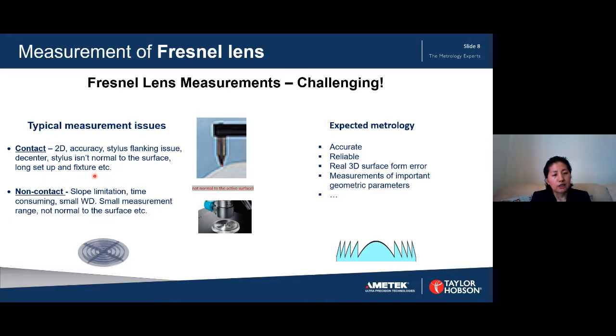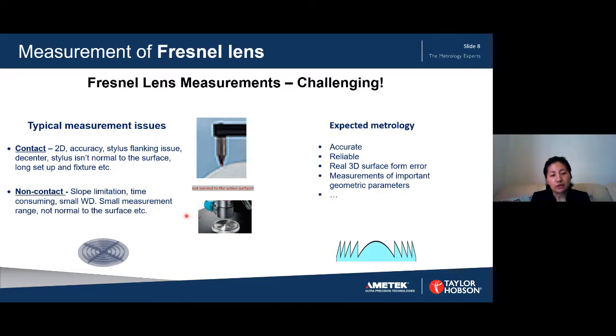For conventional non-contact techniques like white light interferometry, there is a significant slope angle limitation. For example, a lower objective lens — a 5x lens — can only measure a few degrees of slope angle. Even for higher objective lenses like 50x or 100x, measurement is limited to up to about 30 degrees for mirror surfaces. The 100x lens also has a very small field of view — only 0.1 mm — and the measurement range is very limited, often sub-micrometer to micrometer level. None of these are ideal for measuring the complex structured surface of a Fresnel lens.